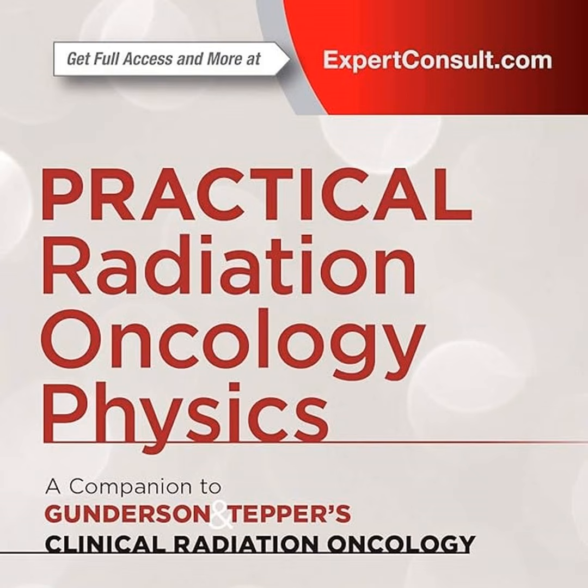And what is so vital to understand about the Scott Jerome Parks tragedy is that the linear accelerator did not break. The machine delivered exactly the amount of radiation the computer told it to deliver. It was a human-computer interface issue, wasn't it? Yes. The failure was a cascade of workflow breakdowns. The treatment plan was imported into the machine incorrectly. Because of a software interface glitch, the heavy lead leaves of the multi-leaf collimator, which shapes the beam to protect healthy tissue, remained completely open instead of conforming to the tumor.